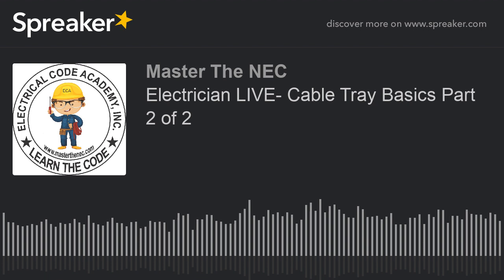All right, so basically it's saying you use the ampacities from those tables for these multi-conductor cables, and of course they'll be modified accordingly based on what we're getting ready to go over, which is A, B, and C of 392.80(A)(1). Number 1 says, the adjustment factors in 310.15(C)(1) shall apply only to multi-conductor cables with more than 3 current-carrying conductors.